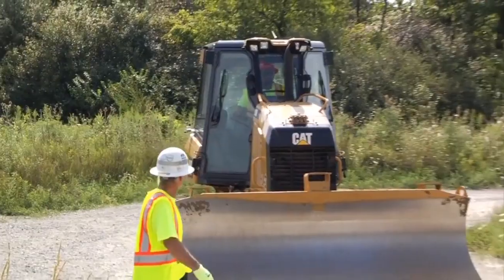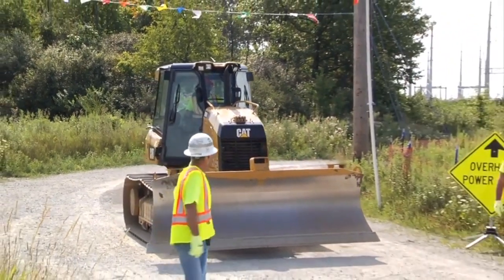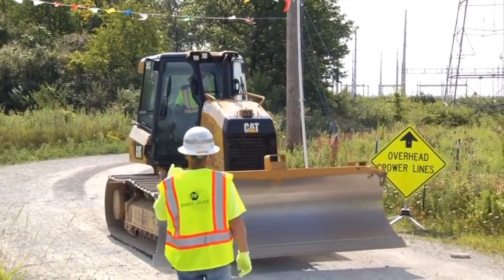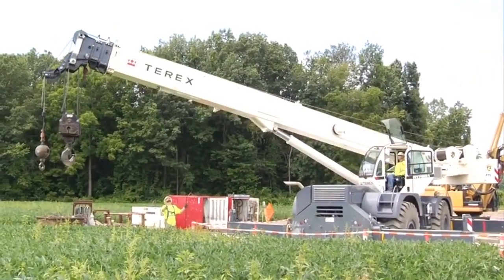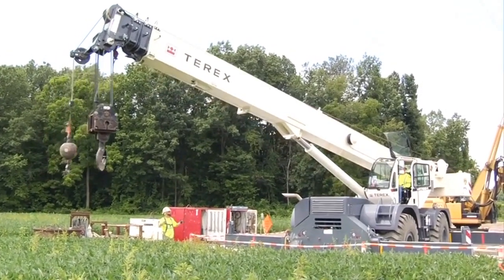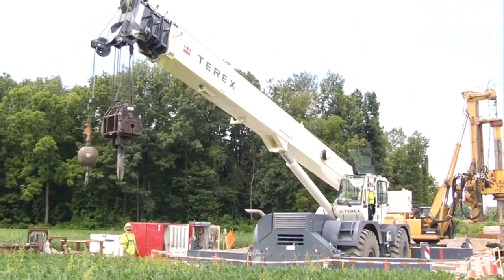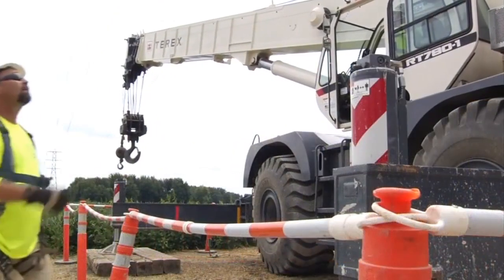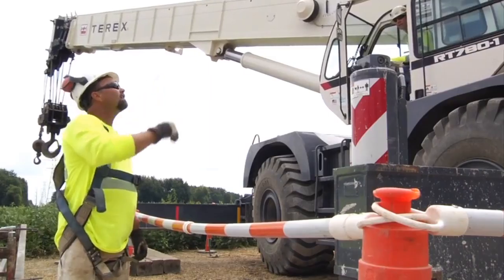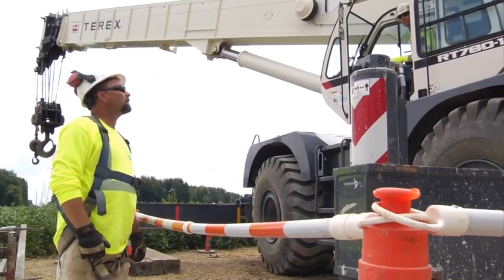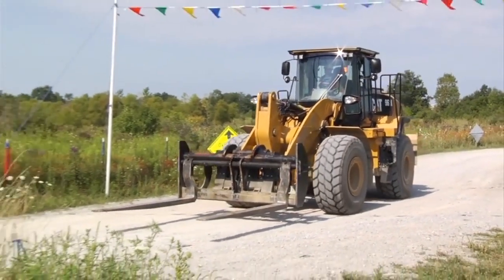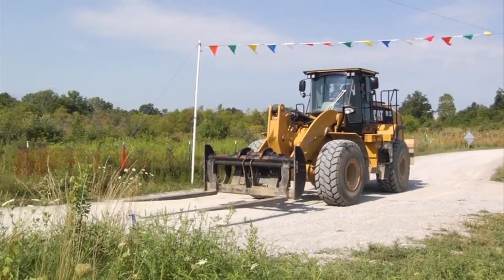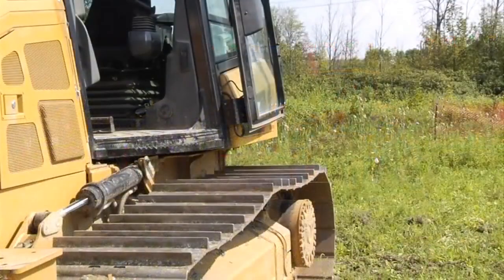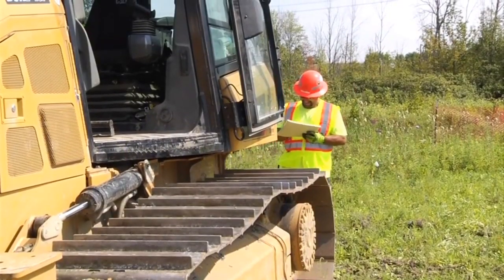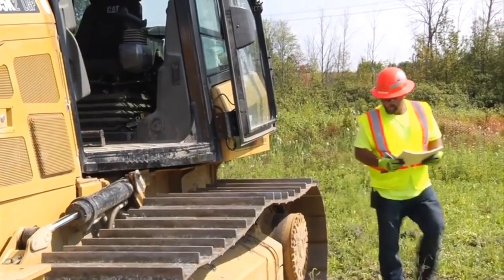And the contractor shall assign dedicated qualified observers if any equipment will encroach within 10 feet while traveling below overhead lines and equipment, or if any part of the equipment's maximum working radius, including the load, load line, boom, and lifting accessories, could encroach the trigger distance. These observers' sole responsibility is to watch the separation between the conductor and the equipment, load line, and load, and to communicate any warnings to the operator and all persons involved in the work. If a qualified observer becomes unavailable, all work activities shall be stopped, even if only temporarily, until the observer is available.